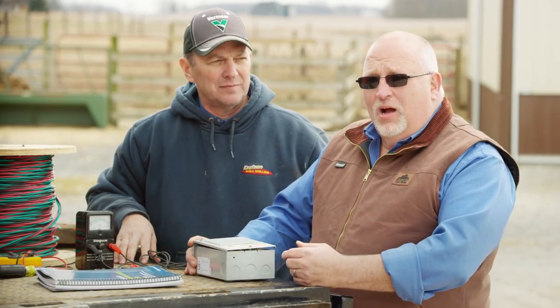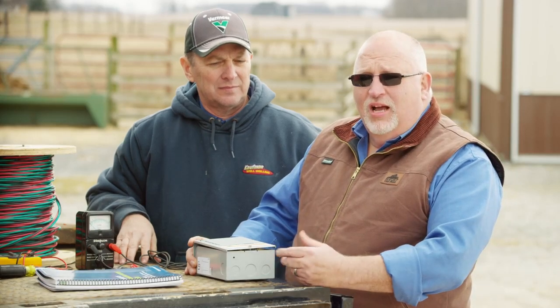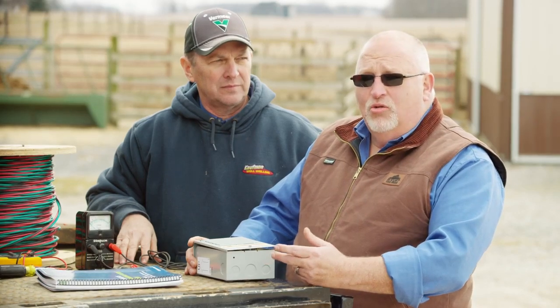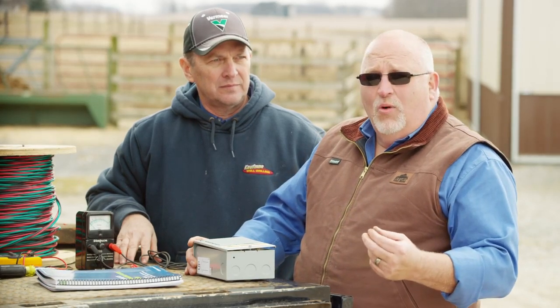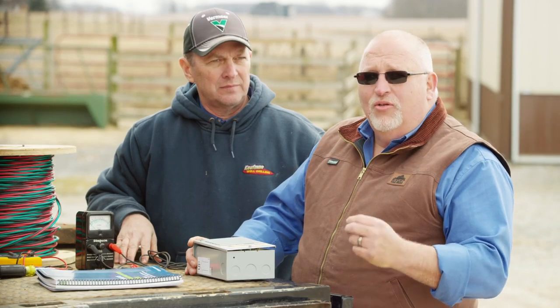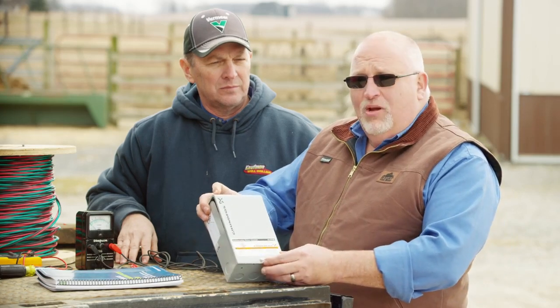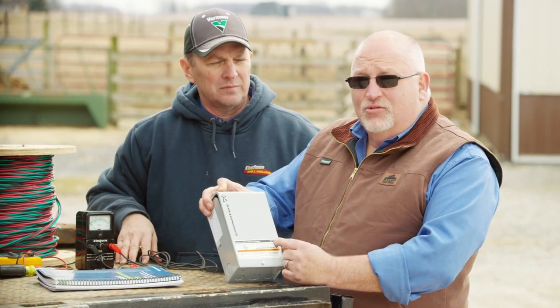Why do we need a control box? Grundfos makes two types of single-phase submersible motors. The first is a two-wire. The two-wire has a start winding and a run winding, and the controls are built into the motor that open the contacts to release the start winding and allow the motor to run continuously with the run winding. Those controls on a three-wire are located inside of a control box.